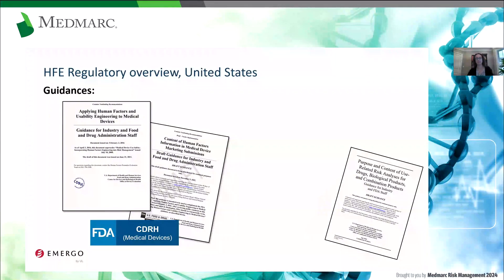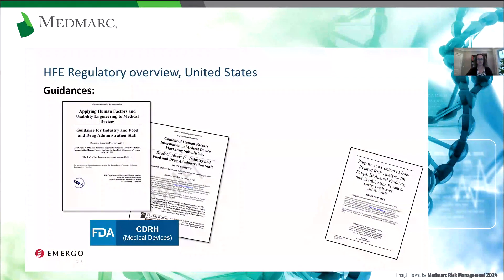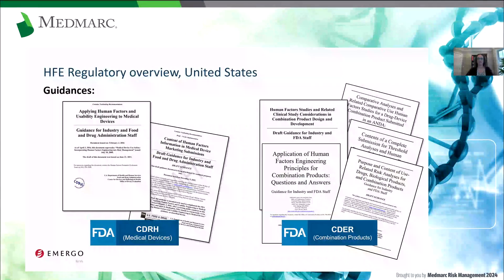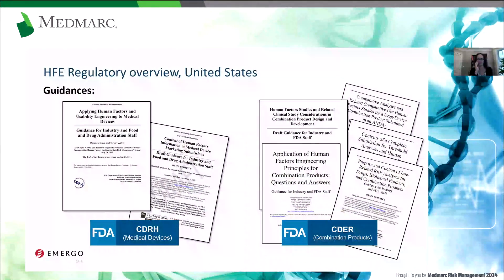The document coming behind it is a draft guidance document that was released in December 2022. This draft guidance tries to provide more clarity to manufacturers on what human factors data needs to be submitted to the FDA along with a given submission. It reflects on things like: is this a brand new product? Are you making design changes to an already marketed and approved product? What is the risk profile? The other set of documents are produced by CDER — the Center for Drug Evaluation and Research — which regulates combination products.